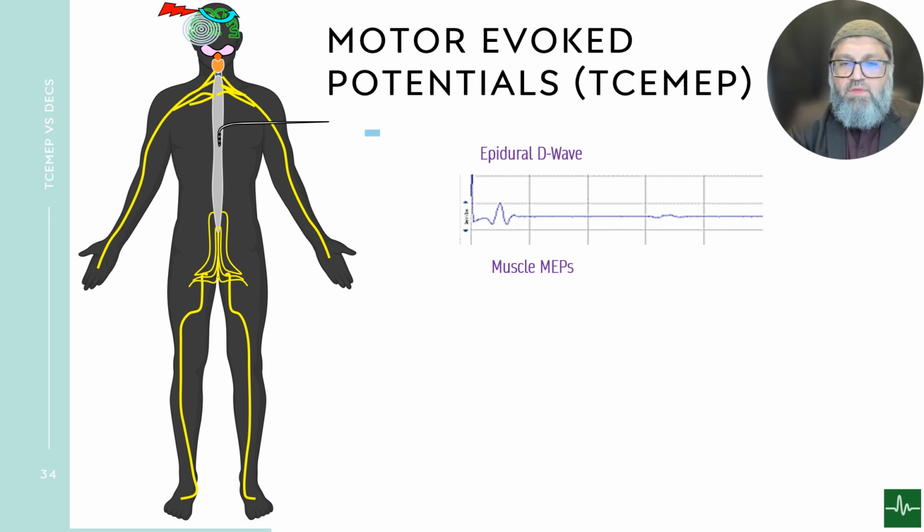When we stimulate, we can do two types of recording, either or both of them. If the spinal cord and dura are exposed, we can use an epidural electrode, which is a grid electrode placed in the epidural space above the dura. In some cases, if the dura is open, you can also place it subdural, but epidural is typical, and those responses are called direct wave responses or D wave responses. The indirect activation of the brain can also cause I waves, which involve more synapses.